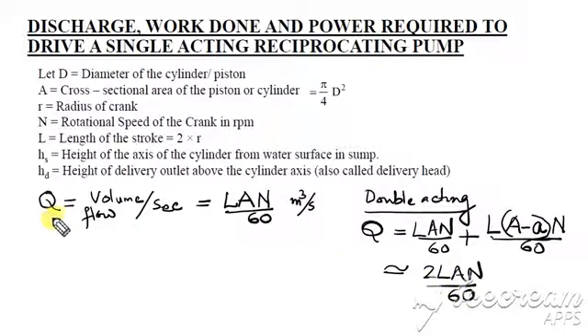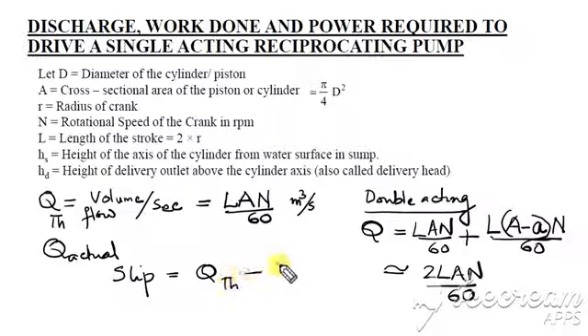This is the theoretical discharge. If the actual discharge of the pump is Q-actual, it may not be the same as Q-theoretical. What we normally expect is Q-actual to be less than Q-theoretical. In that case, we introduce a term called slip, which is essentially Q-theoretical minus Q-actual.